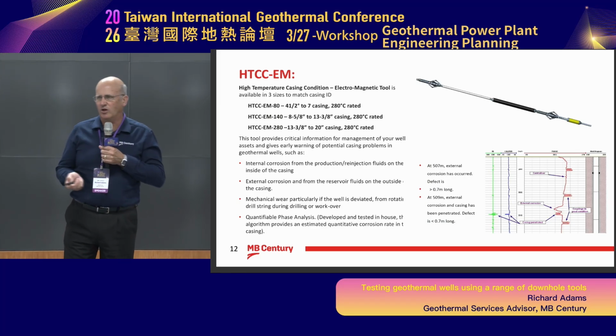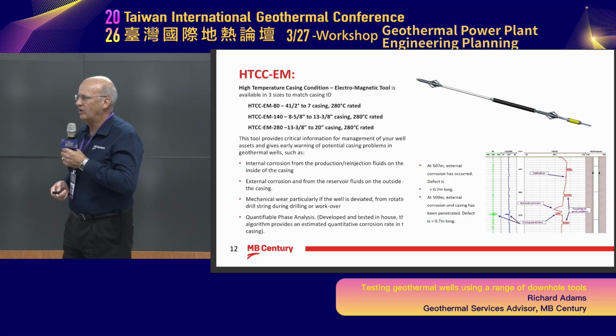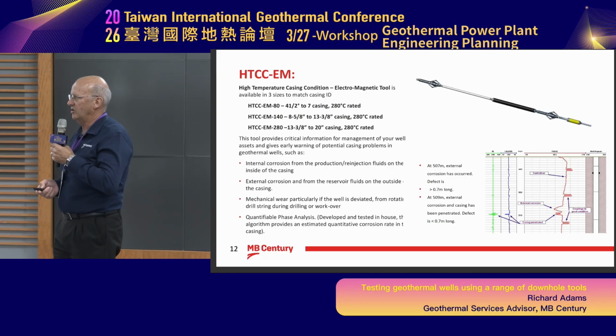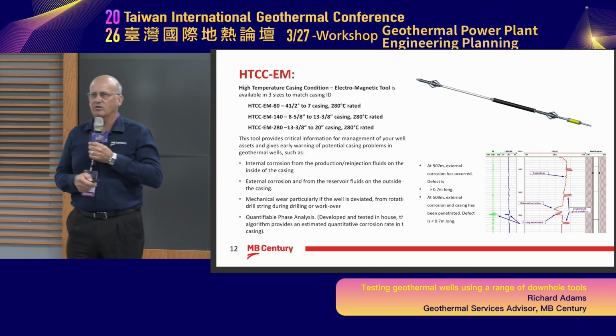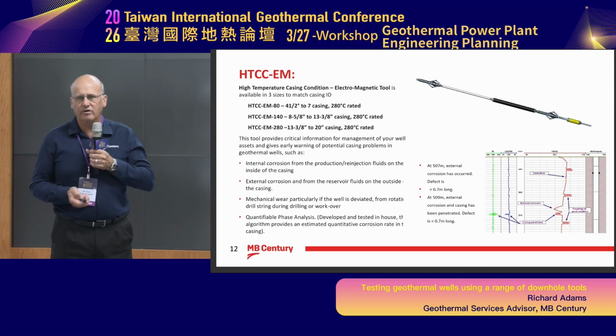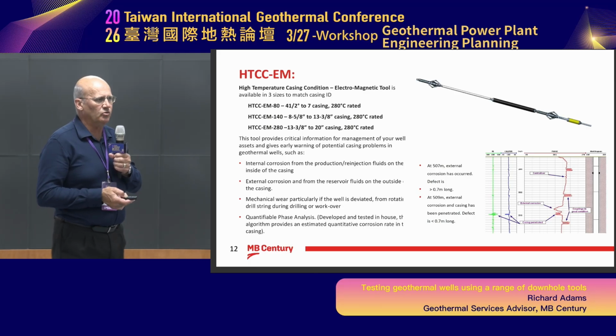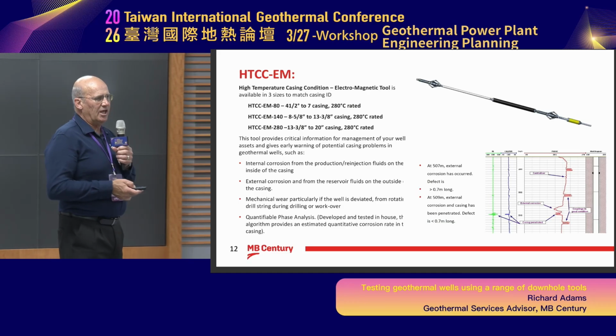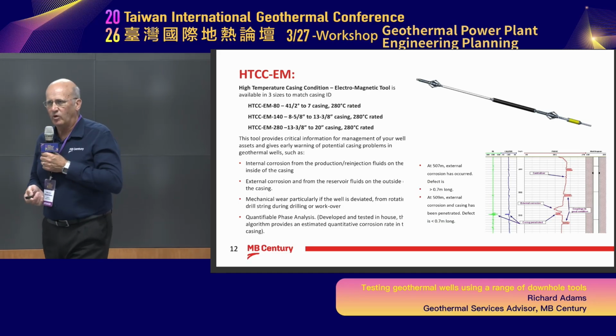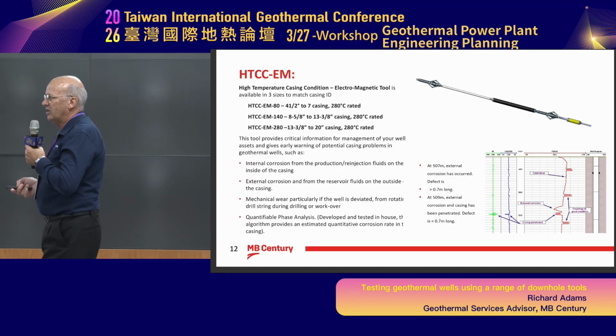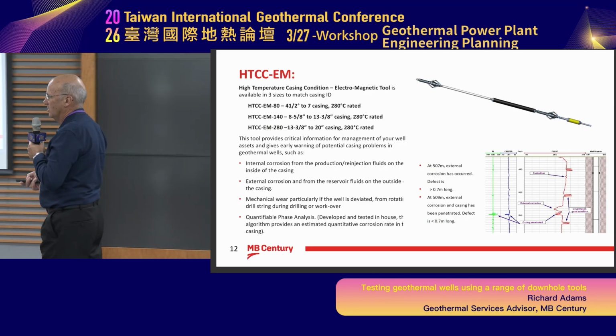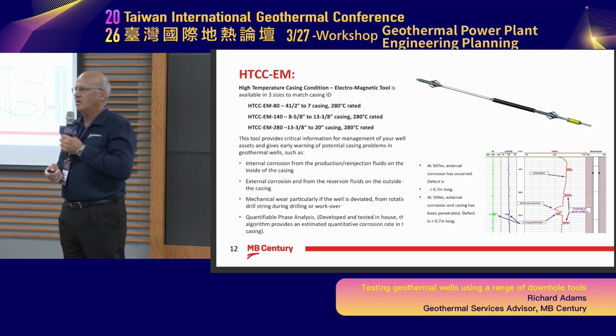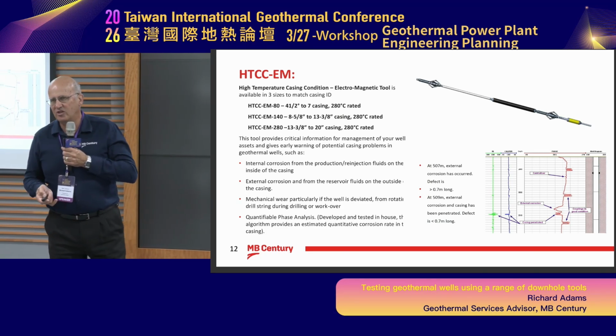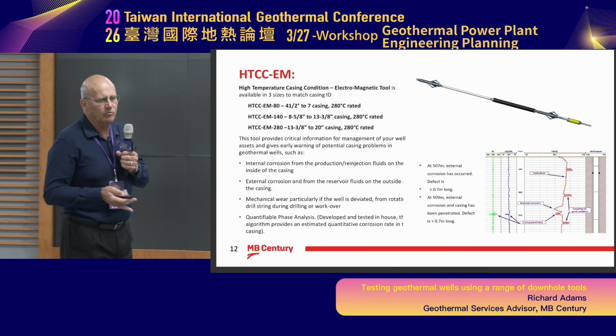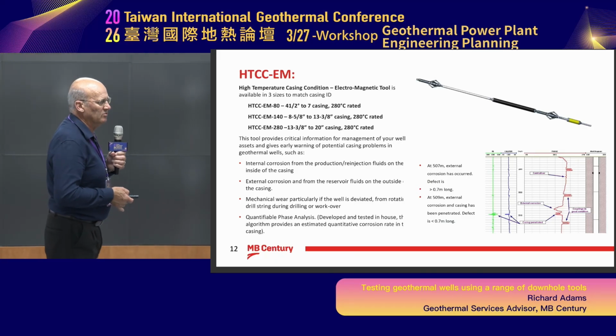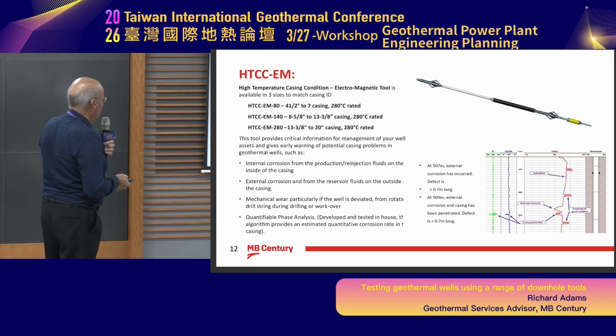We've seen wells in New Zealand from 5 years destroyed, eaten halfway through because of volcanic ground conditions that ate through the cement and caused corrosion issues. They did a workover and then had to decide whether to keep the well. I was last week on a drilling pad with 6 geothermal wells, all producing - one right in the middle has a corrosion issue. So how do they mitigate that? They're actually injecting condensate into the fluid, into the field, to help neutralise the natural formation issues. We've had to come up with all sorts of solutions.